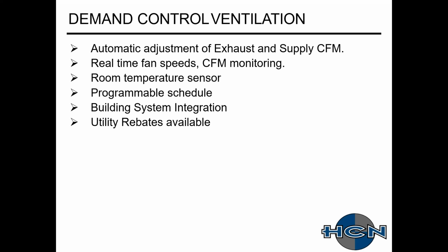Okay. Do the exhaust fans need to run when the Ansul system is discharging? Yes, that code is required. Typically, if you had a fire and let's say no one was there, the control mechanism actually would kick on the exhaust fan and make sure that's running. Your makeup air is actually cut off. So per code, you have to have the fan running for most jurisdictions. There's some weird ones here and there; the last time I had something like that was an Indian reservation in Arizona. Okay. For the most part, exhaust fan needs to run on this fire as well.